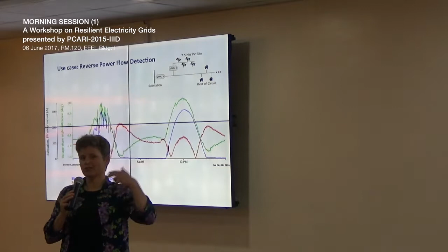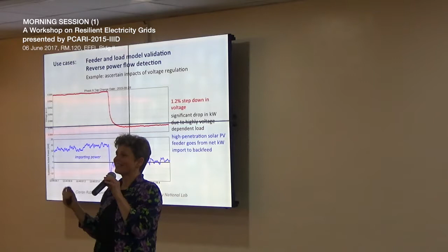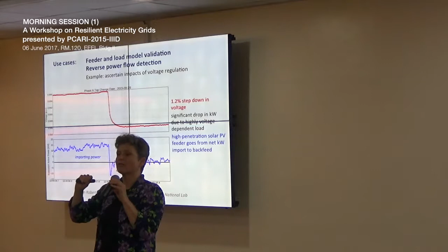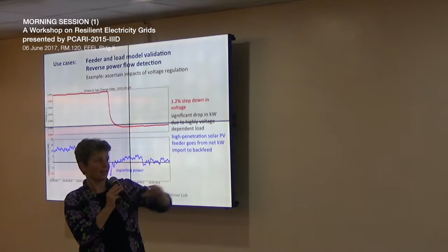There's something else interesting: when the current is close to zero, if a tap changer operates, the customer load—being sensitive to voltage, as in zip load models—responds. If the voltage steps down, some loads reduce their power demand by different percentages. On this circuit, that reduction in load from the tap change down was enough to reverse the whole power flow on the feeder. Again, not something you ever would have known was happening.